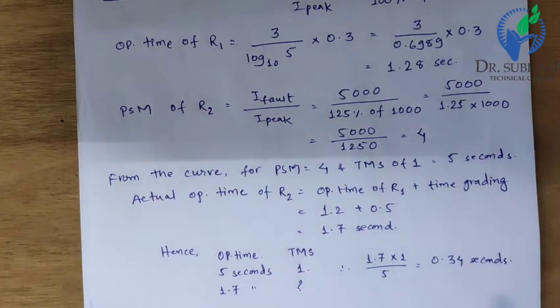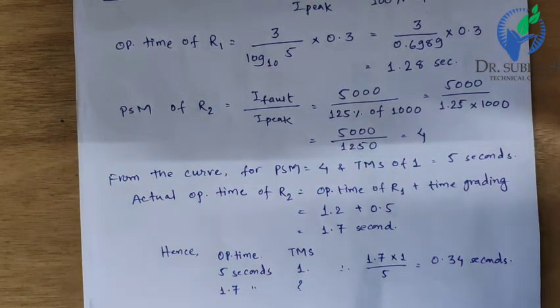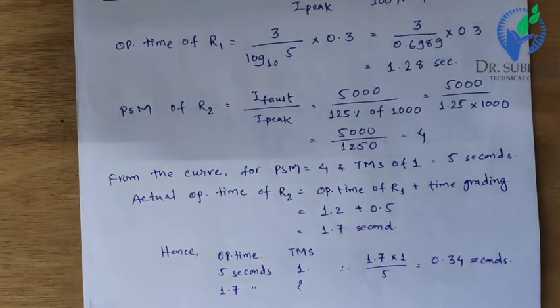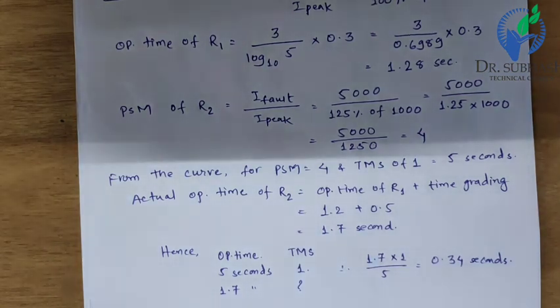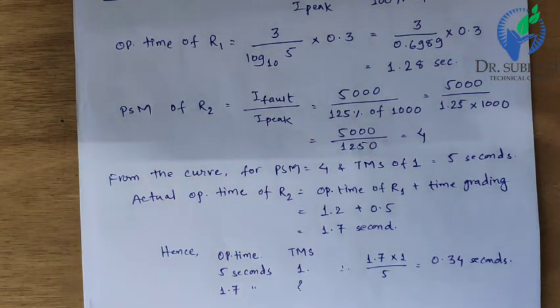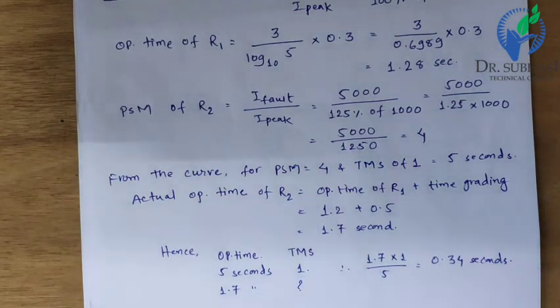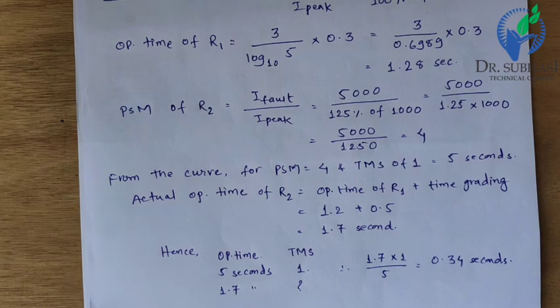In conclusion, R1 operating time is 1.28 seconds. After adding the discrimination time grading of 0.5 seconds, R2 must operate at 1.7 seconds total, requiring a TMS of 0.34 for R2. Thanks everyone.